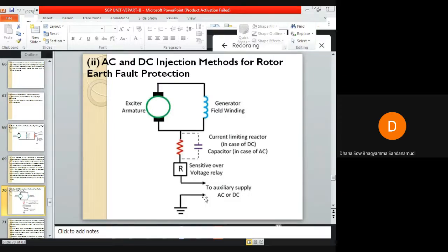Okay, so instead of injecting AC supply, I can inject DC supply. This method of protecting the rotor against earth faults by injecting DC supply is more simple, and there is no problem of leakage currents. Here, when I am giving DC supply, one terminal of this sensitive relay is connected to this exciter, and the other terminal is connected to the negative terminal of this DC source, and the positive terminal of this DC source is grounded.